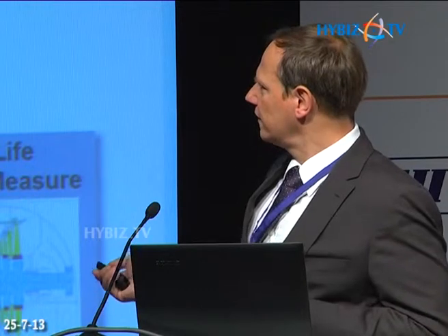Latest by the technical design time, after 200,000 operating hours, you would want to do this inspection and then identify what measures are required. There's a little process to come to the results of this lifetime assessment study, which is: first you do the NDT test, then you do the evaluation of your operational hours, the historic ones, as well as a future regime.